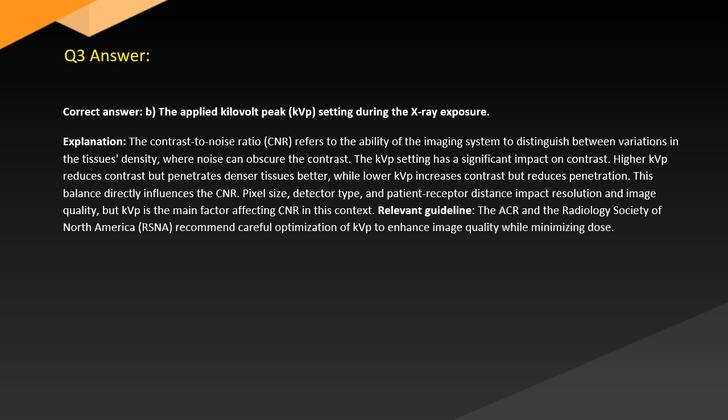Pixel size, detector type, and patient receptor distance impact resolution and image quality, but kVp is the main factor affecting CNR in this context. Relevant guideline. The ACR and the Radiological Society of North America (RSNA) recommend careful optimization of kVp to enhance image quality while minimizing dose.